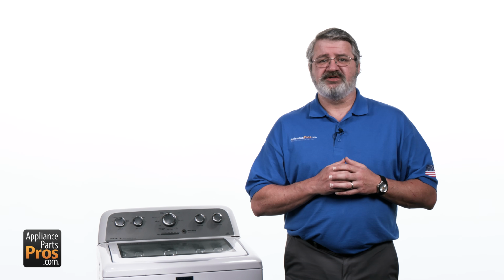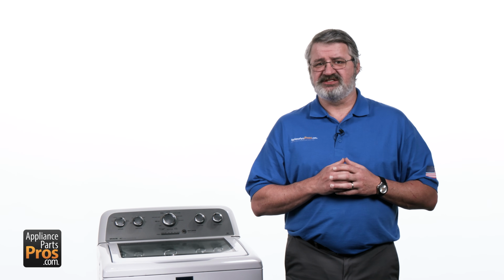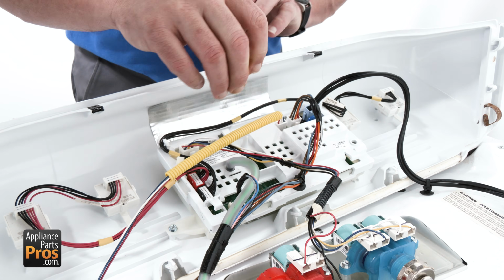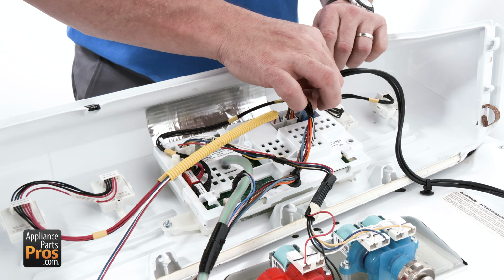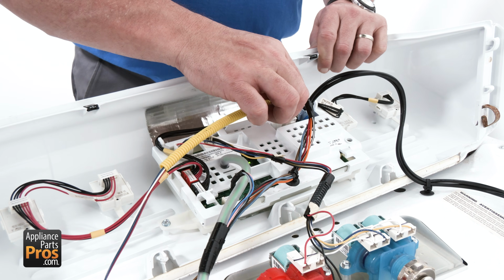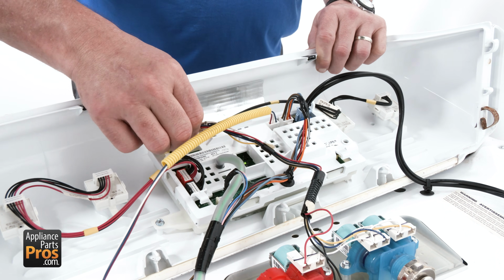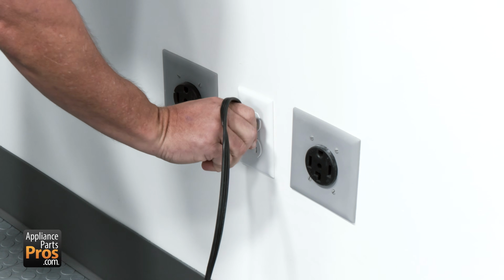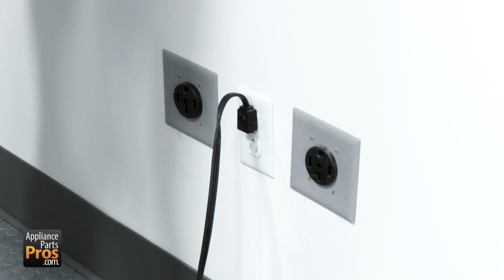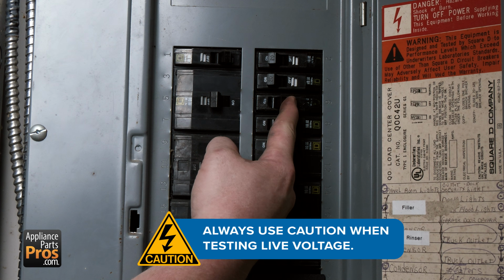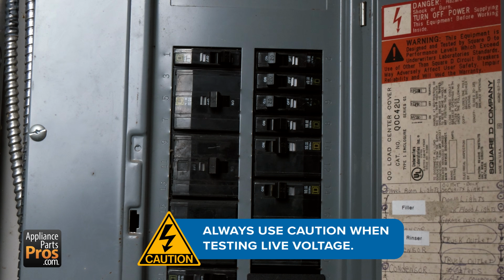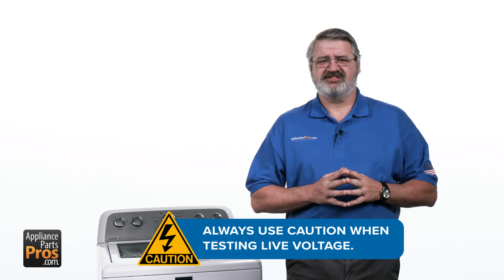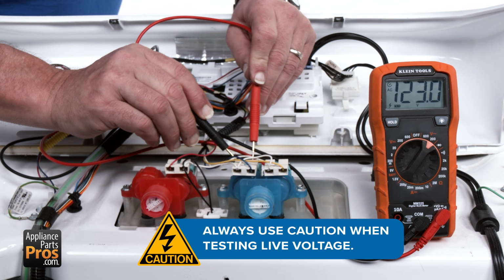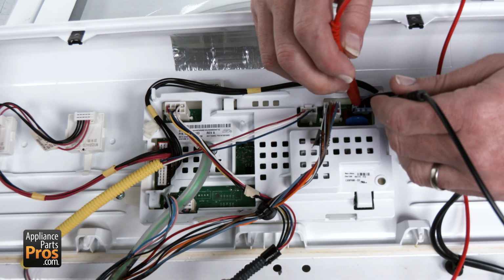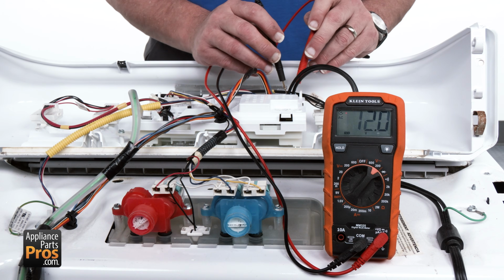Next, we'll verify that the control board and its built-in pressure sensing system are operating correctly and inspect all wiring connections at the control board, making sure each connector is fully seated and not damaged. Once everything checks out, restore power and test for proper incoming voltage at the control. Extreme care should always be taken to protect against electric shock, which could potentially result in serious injury. Please do not test line voltage if you're uncomfortable using a multimeter around live voltage. You should measure approximately 120 volts AC between L1 and neutral.